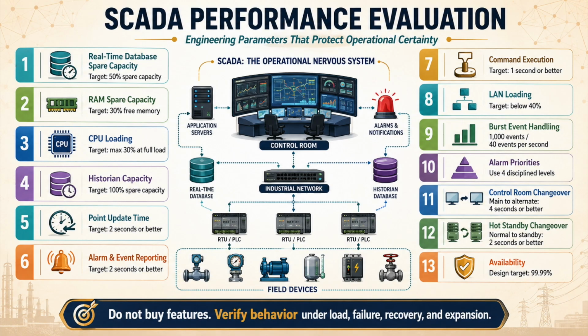The ninth engineering parameter is complete point update time, because a 2-second update boundary is not only a speed metric, it is an operator confidence boundary. And when operators trust that screens reflect the process, they act decisively. But when they suspect delay, they hesitate, cross-check, call the field, delay commands, and lose confidence in the control room picture.